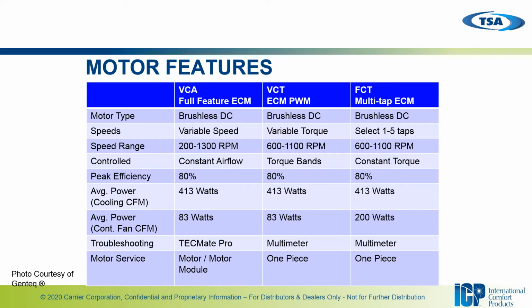All right, so let's get to the nitty-gritty and talk about the features of each motor. First, we'll talk about the variable constant airflow. It is a brushless DC motor, a true variable speed motor, which we'll talk about more in a few minutes. It has a speed range of 200 to 1300 RPM. It is a constant airflow motor with 80% peak efficiency, an average power rating in cooling mode of 413 watts, and average power in constant fan mode of 83 watts. It can be troubleshot with the TECMate Pro motor tester and is actually a two-piece motor, so the motor and module are separate.